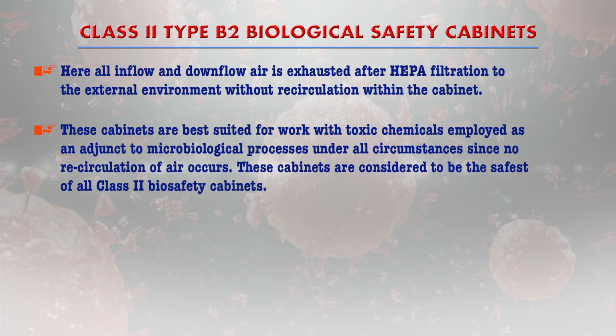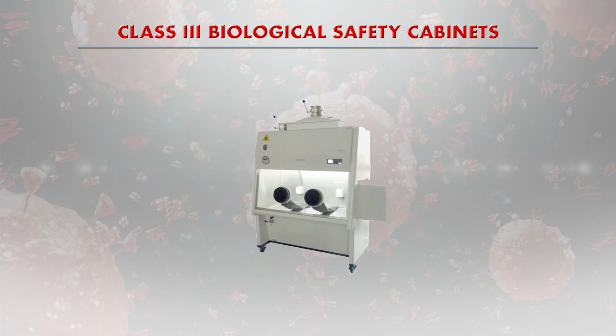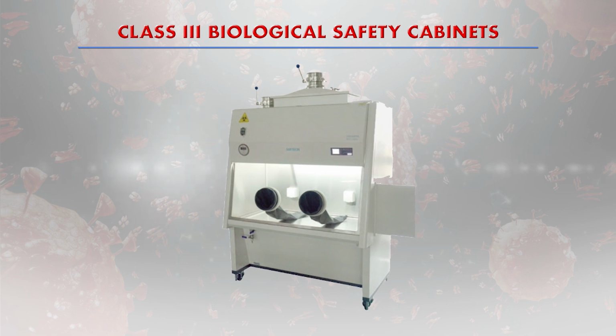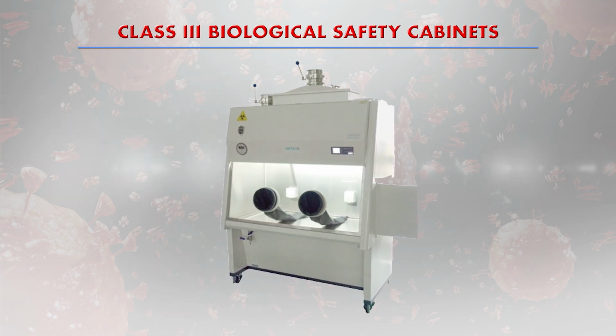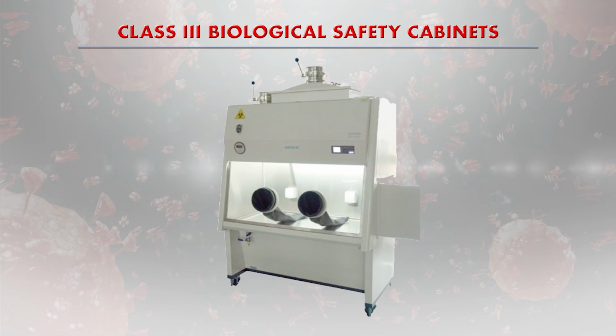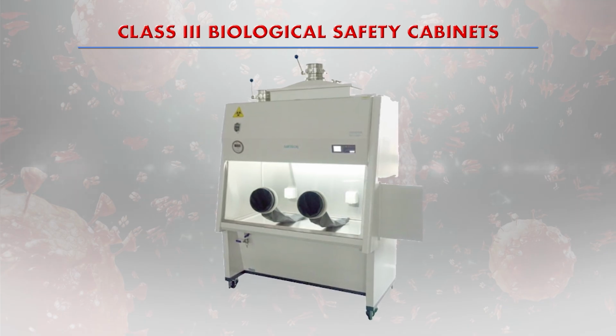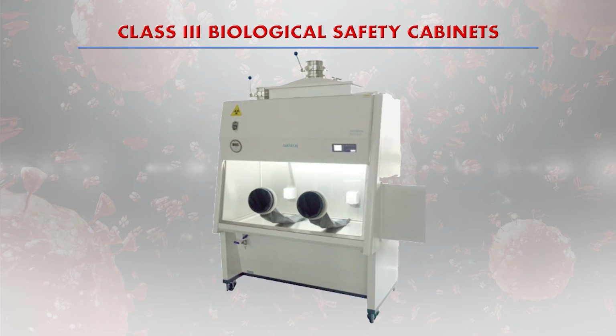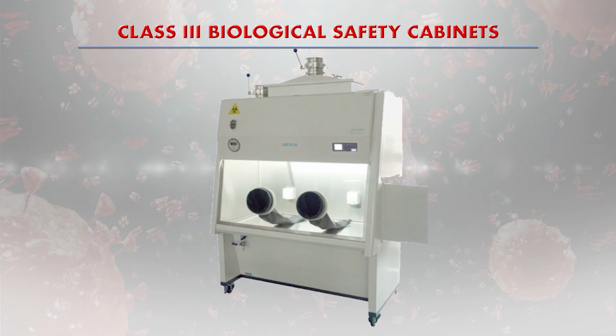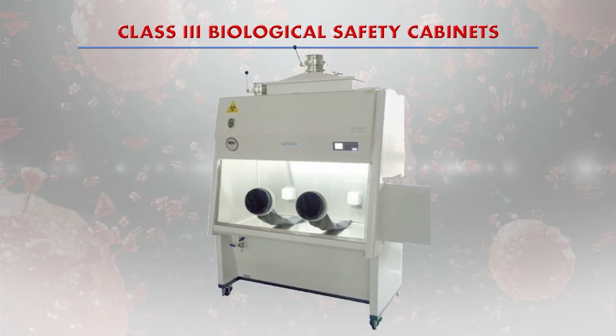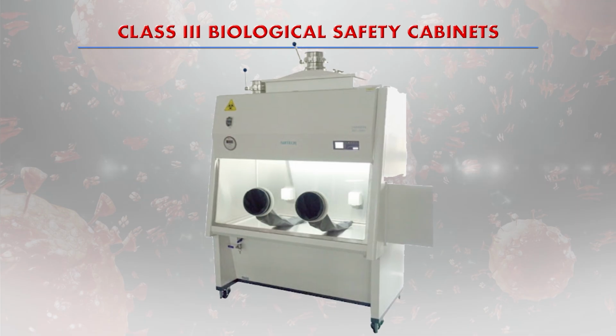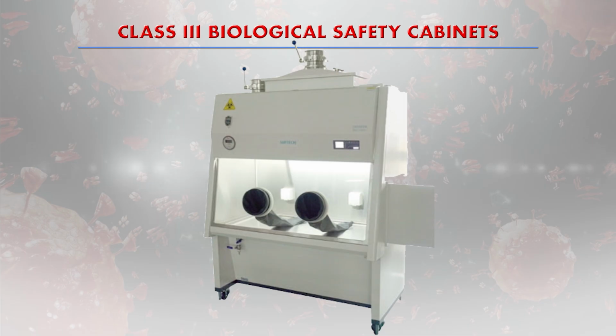So these cabinets are considered to be the safest of all the biosafety cabinets. The class 3 biological safety cabinets. From this figure itself you should understand that these are the most safe, absolutely safe cabinets, which are usually employed when you are dealing with highly hazardous, the most contaminated and infectious microbiological agents.